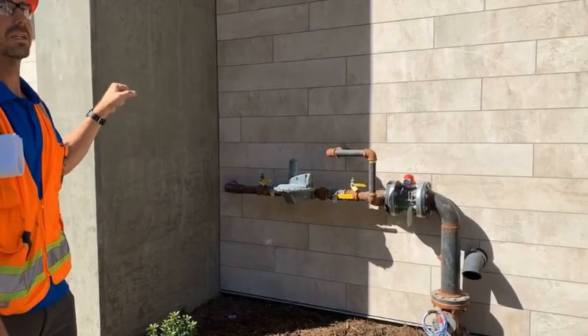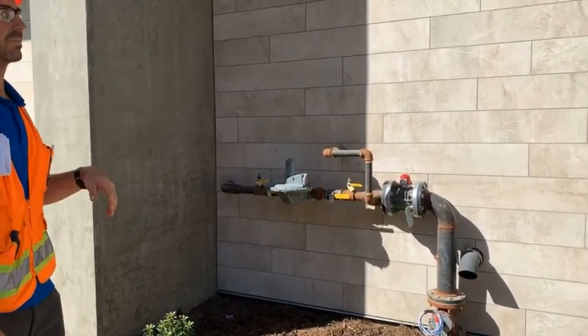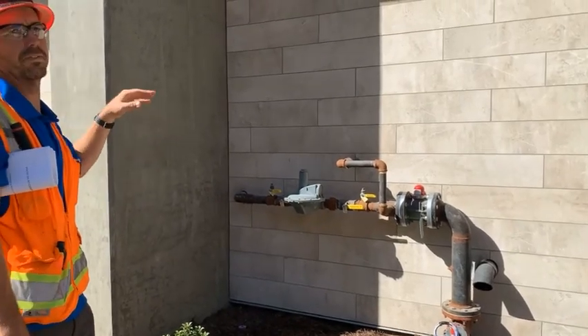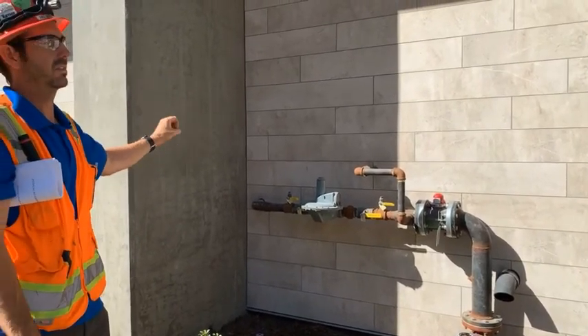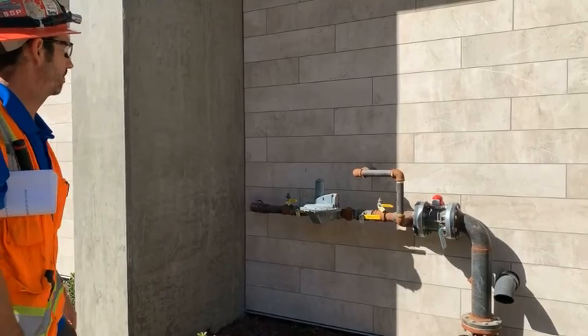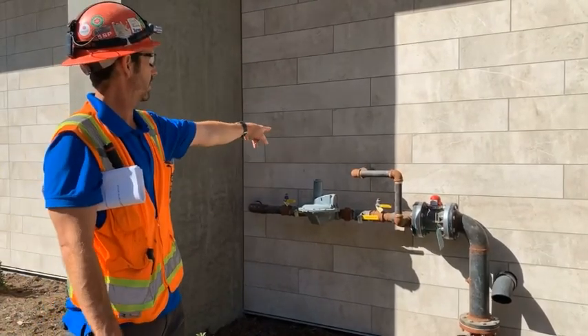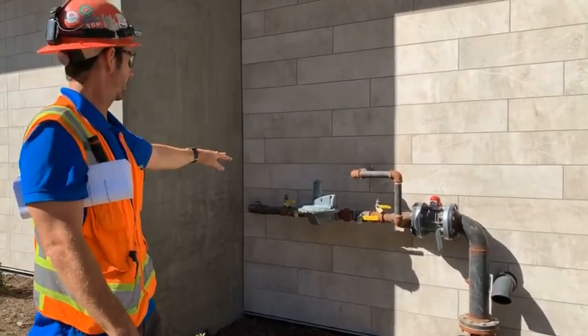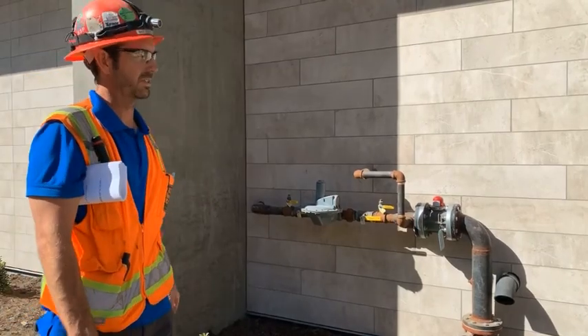But even though we're not going to use it, the gas is going to the lobby kitchen there, right? Yeah, we can double check the drawings for the final locations of all the gas lines. We know where they are. It's the low pressure line for the apartments and laundry room. Medium pressure comes off before the regulator feeding the boilers. All the other stuff is off of the low pressure.